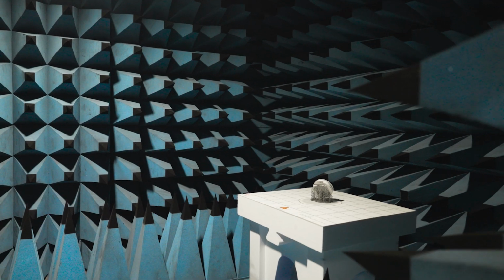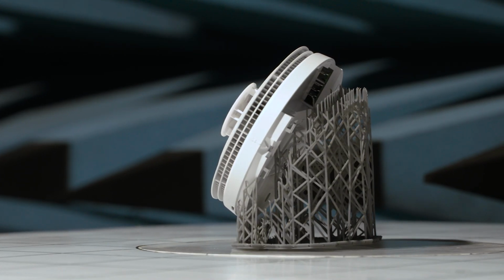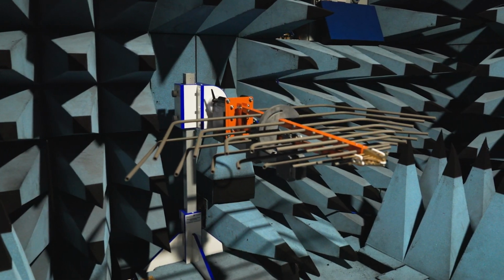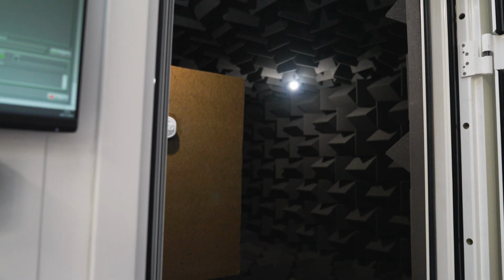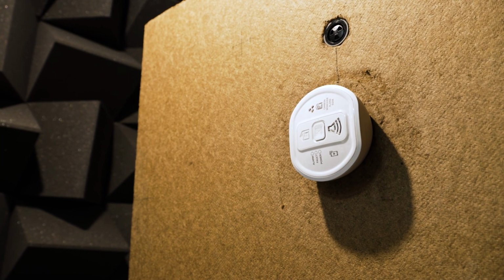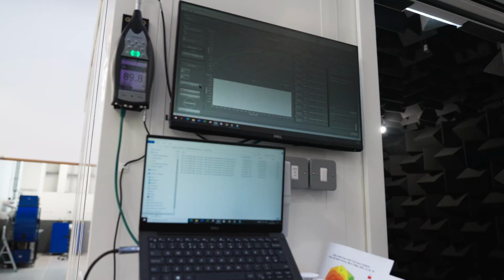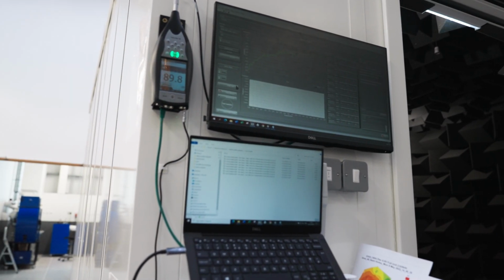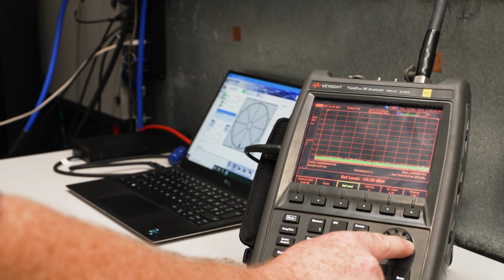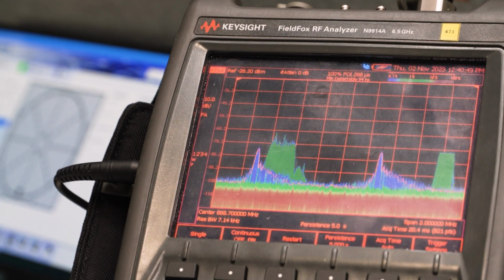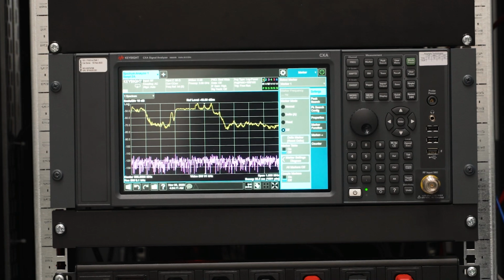And then we can bring them to all of the chambers we have. Our RF test chamber allows us to isolate our units under test from interference from other devices that could exist in the field. The sound chamber allows us to characterize a unit in a similar way that we can rotate the tables on our RF chamber. We can also rotate the tables that our device is fixed to in the sound chambers. In a 23-minute test, 1.6 million sound measurements to create a really detailed image of how our unit is performing in terms of sound output.